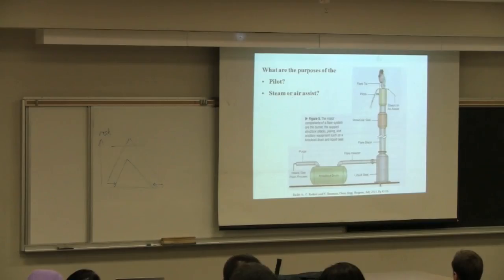There's always sound produced by a flame, so they'll have tubes there to take the sound, and that's monitored. You can monitor it by heat, with a thermocouple in the pilot's path. You can monitor the ionization, since the flame has a lot of ionized particles. And you can use infrared sensors to monitor the presence of the pilot. Infrared cameras are very common for this.